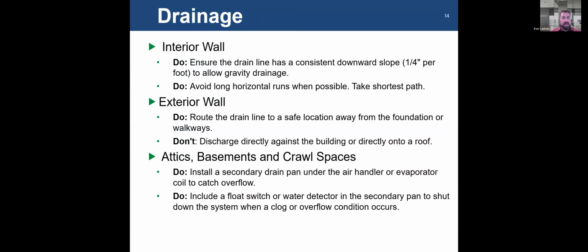If you come across a case where you did have to put a condensate line onto the roof, which is not really recommended, make sure you have a protector underneath it. Otherwise, that constant dripping from the condensate will wear away the roof. When installing units, and this really has nothing to do with mini splits or anything like that, when installing units in attics, basements, crawl spaces, make sure you put a secondary drain pan underneath that air handling unit or evaporator to catch any kind of overflow or spills that may happen.